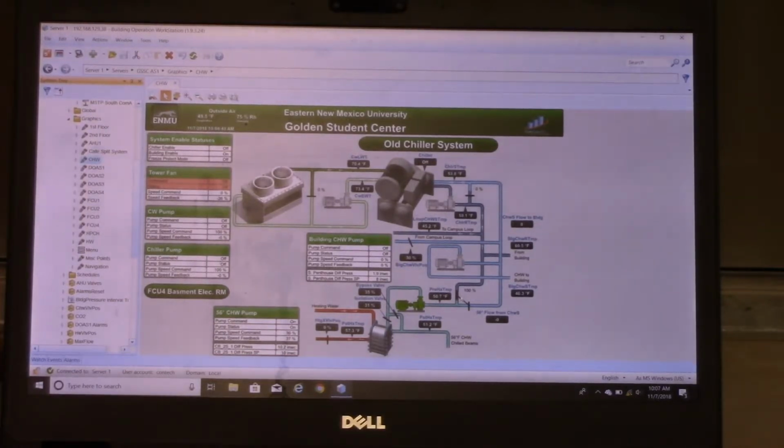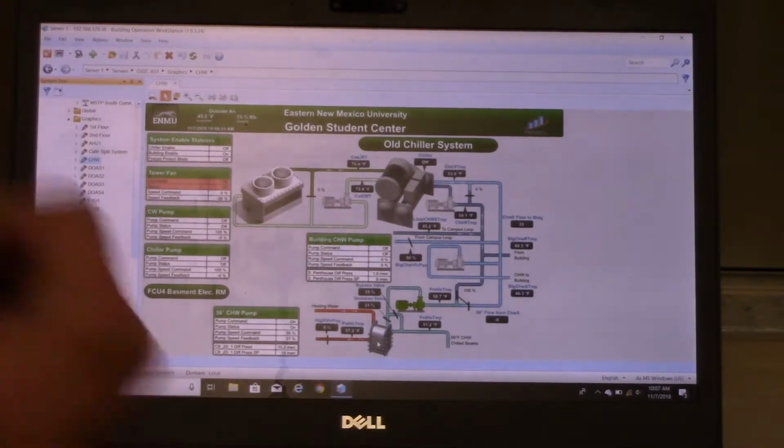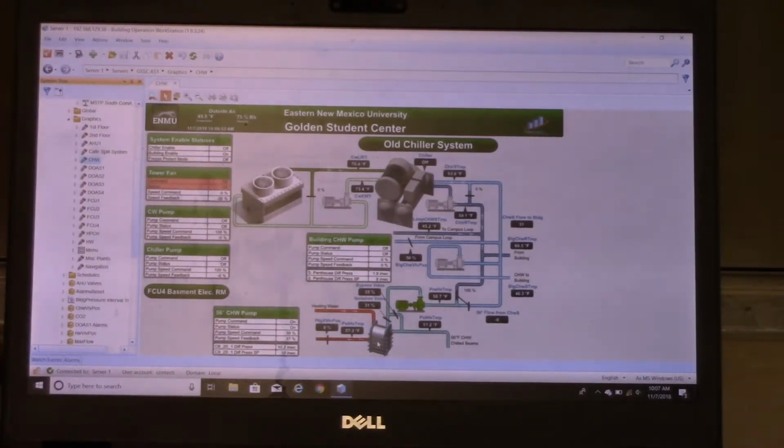So that's the first attempt at getting this warmer, is start to pull return chilled water from the building. If that can't do it, you have a heat exchanger that'll begin to modulate hot water through the heat exchanger, excuse me, to warm that water up to 56 degrees.